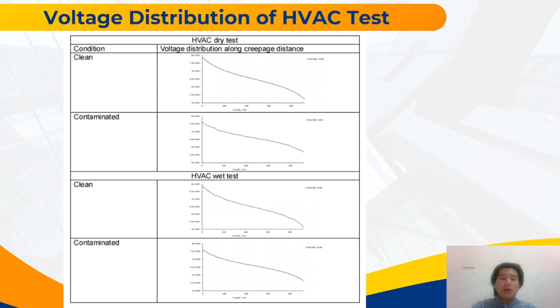Moving on to the electric field strength distribution for the HVAC test, we again tested clean and contaminated conditions under both dry and wet states. The difference is mainly visible between dry and wet conditions: the electric field strength along the creepage distance is higher in dry conditions, for both clean and contaminated cases, than in wet conditions. As shown here, the dry condition graphs are clearly much higher than the wet condition graphs.